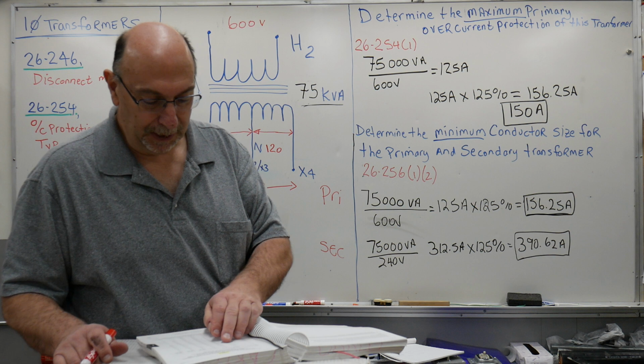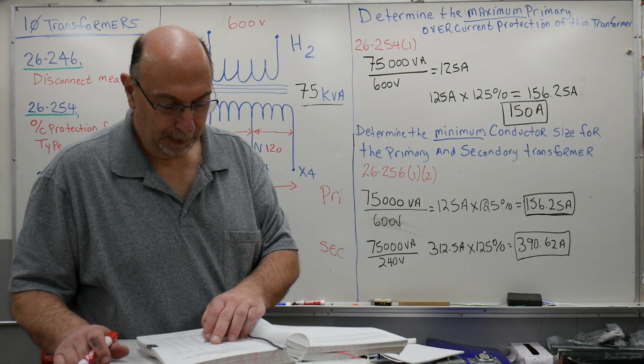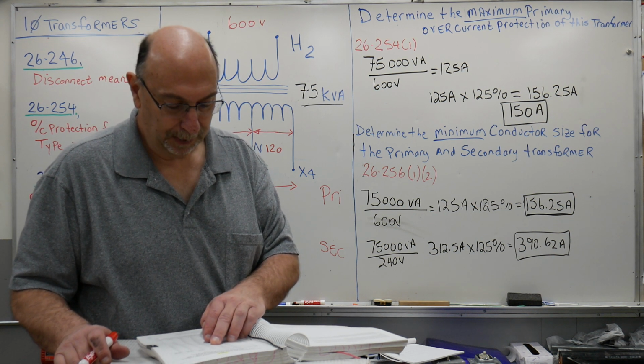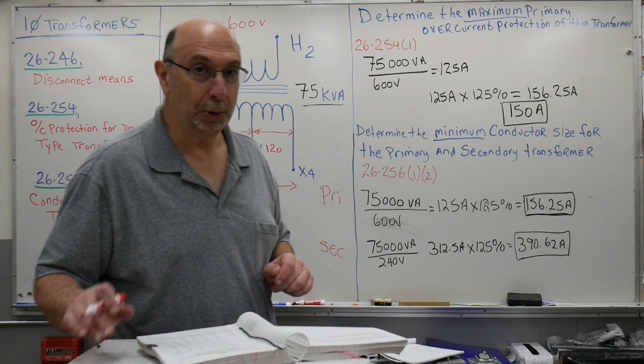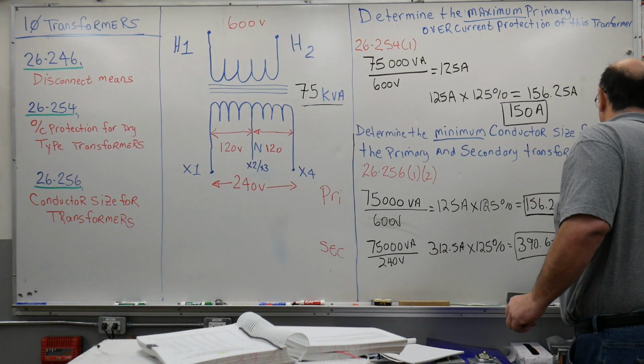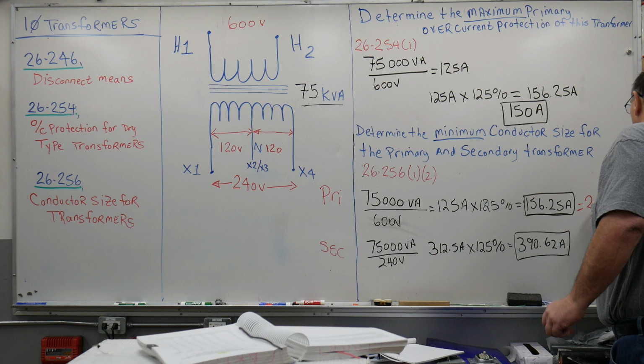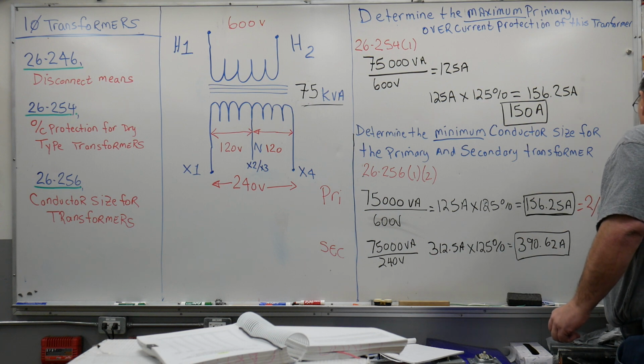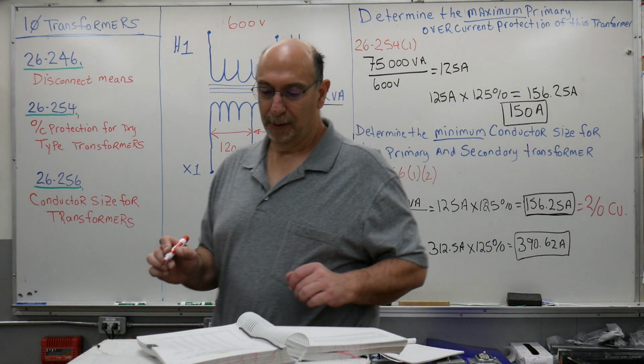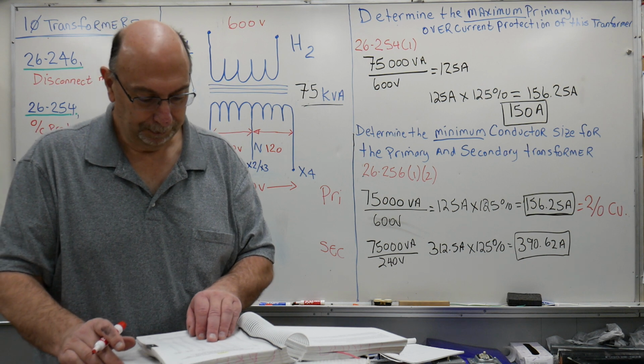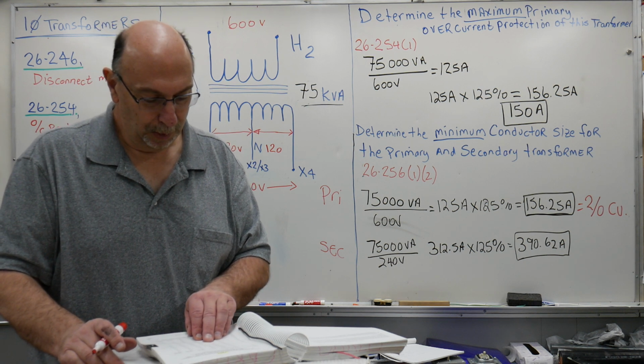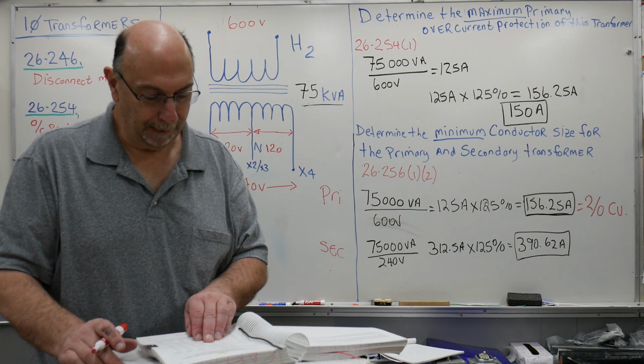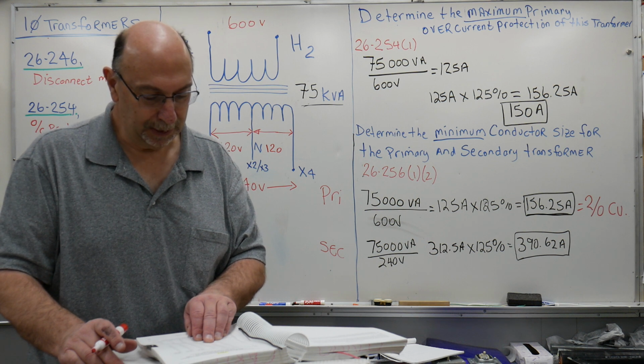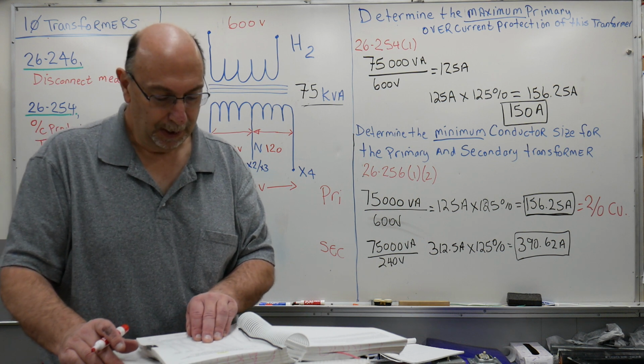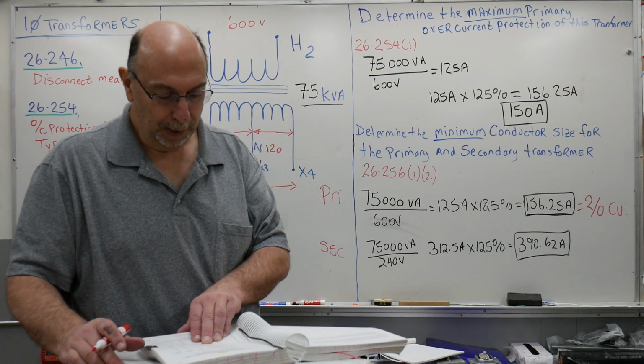So 156.25 puts us up to the 2/0. The 390, ooh, geez, we just missed the 500 because that is good only for 380 amps. We have to go up to 600 kcmil.